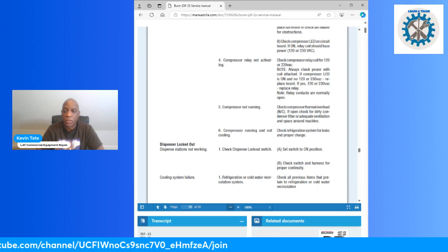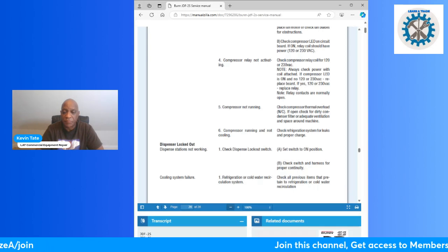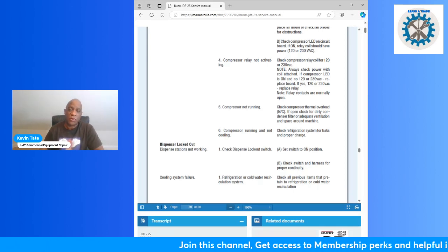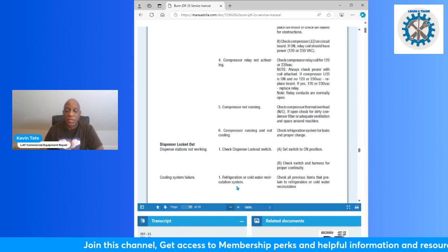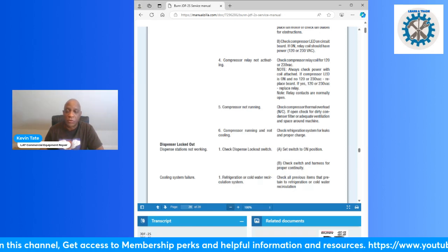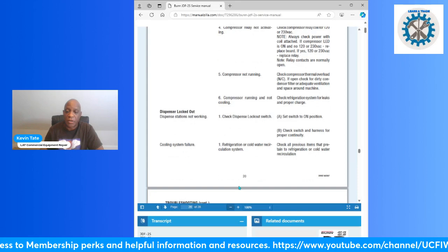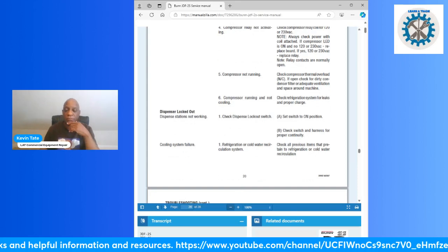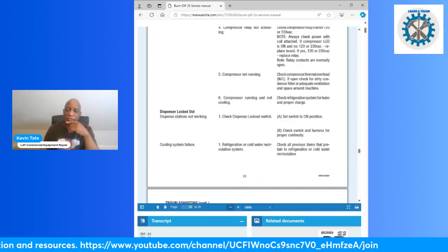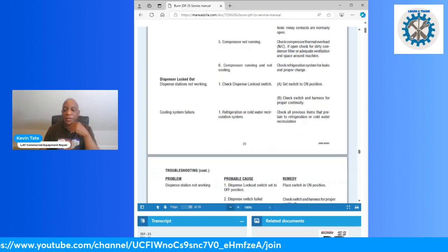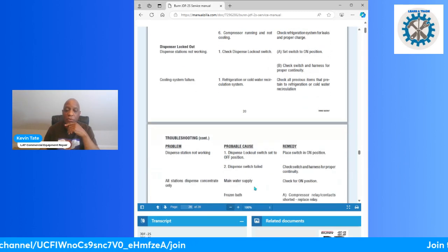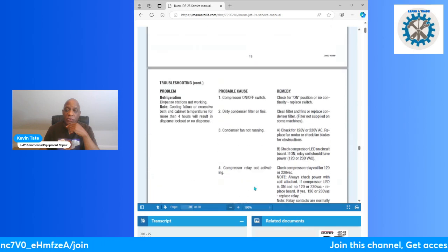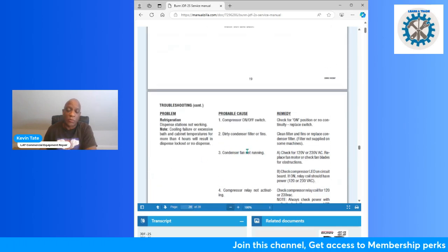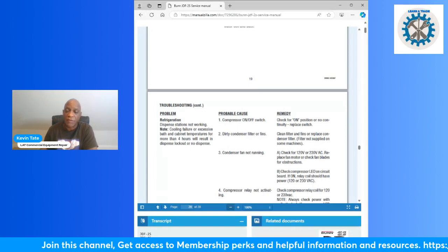So just, you know, check all of that out, and let me know what you ran into, because it could be a few things. It's possible you could have a bad temp probe. I mean, that happens from time to time, but it's not very common. So I would first look into the refrigeration issues with that compressor problem that you're having.